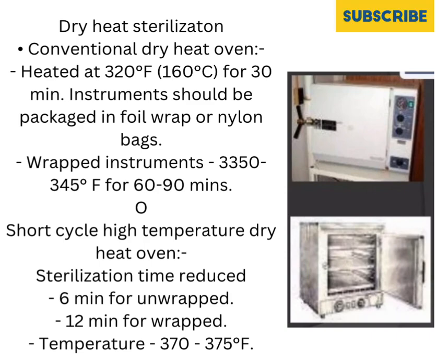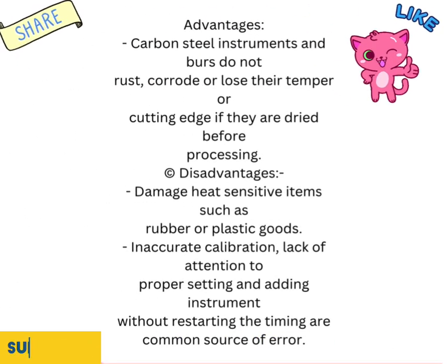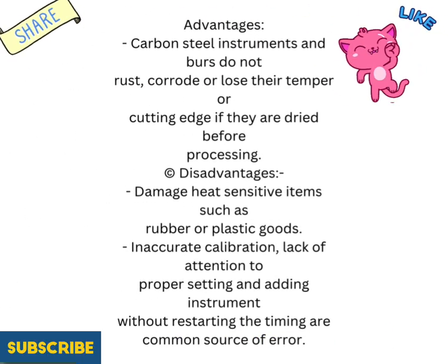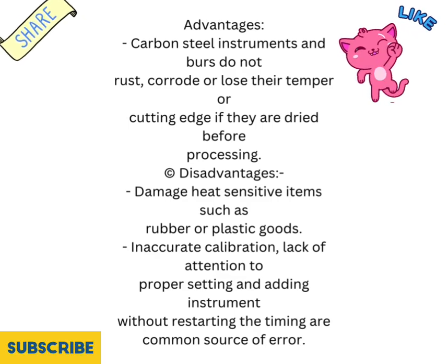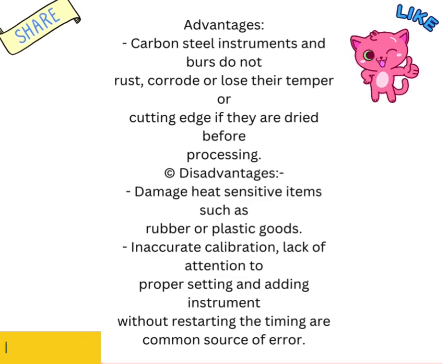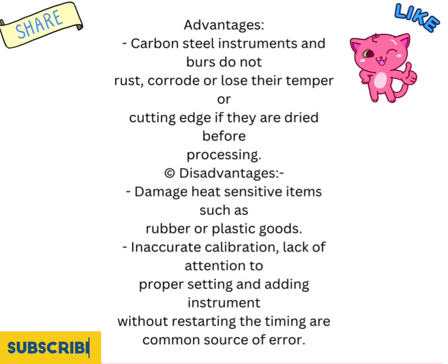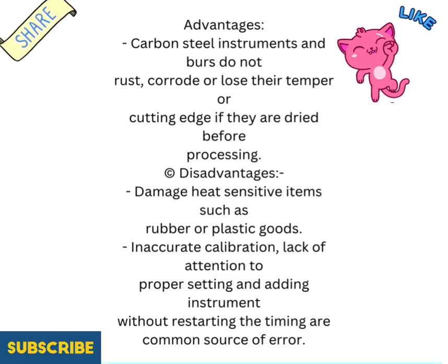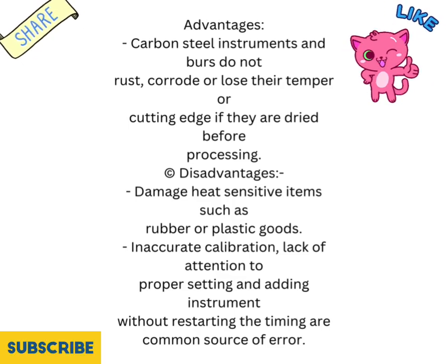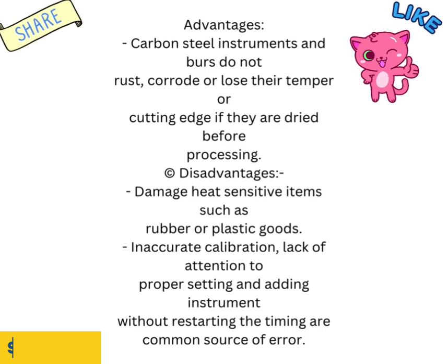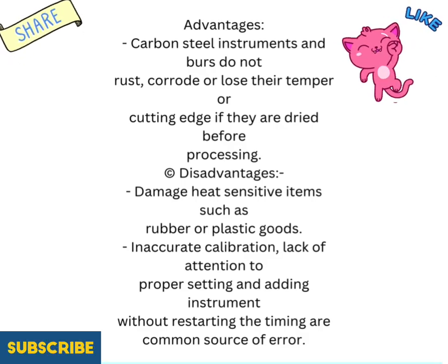Short cycle high temperature dry heat oven. Sterilization time reduced: 6 minutes for unwrapped, 12 minutes for wrapped. Temperature: 370-375 degrees F. Advantages: carbon steel instruments and burrs do not rust, corrode, or lose their temper or cutting edge if they are dried before processing. Disadvantages: damage to heat-sensitive items such as rubber or plastic goods. Inaccurate calibration, lack of attention to proper setting and adding instruments without restarting the timing are common sources of error.